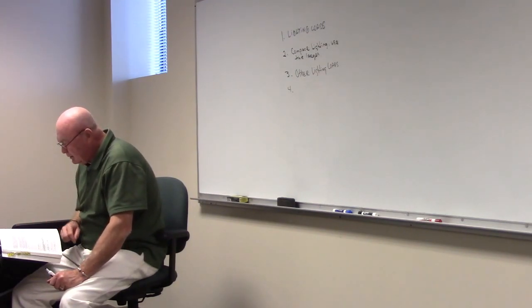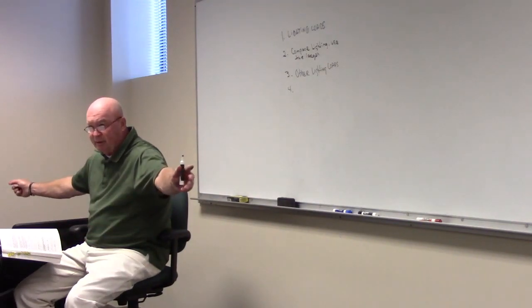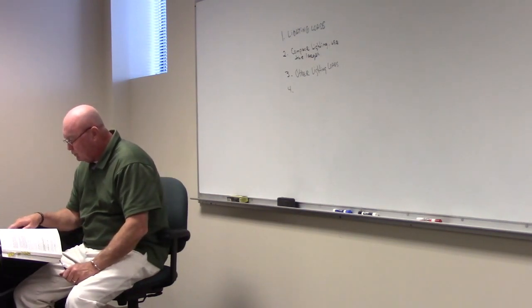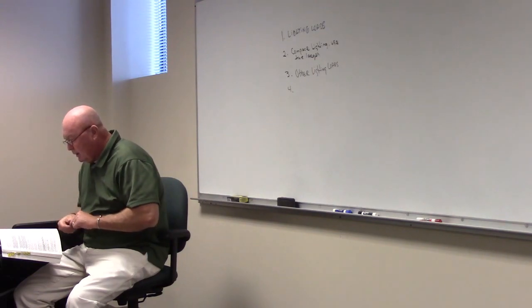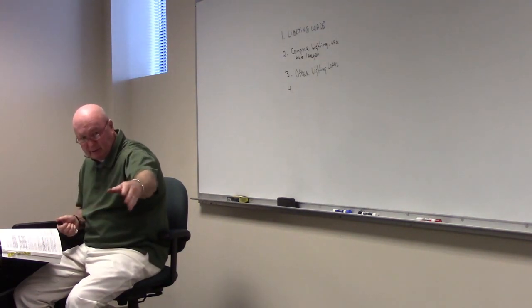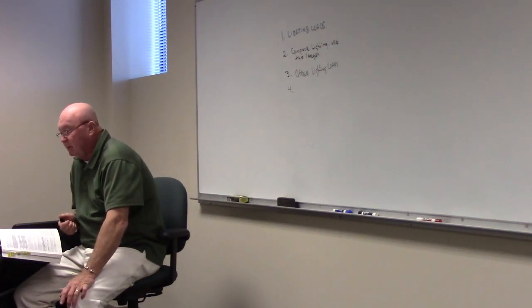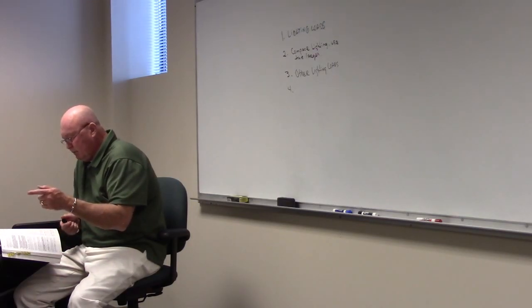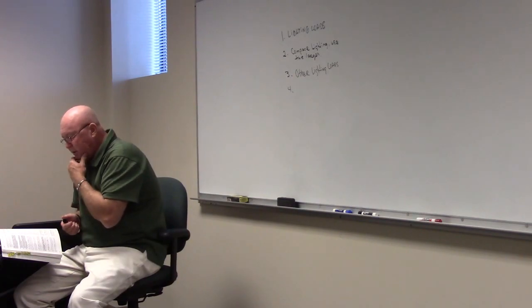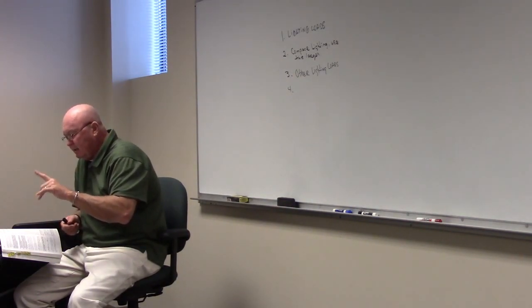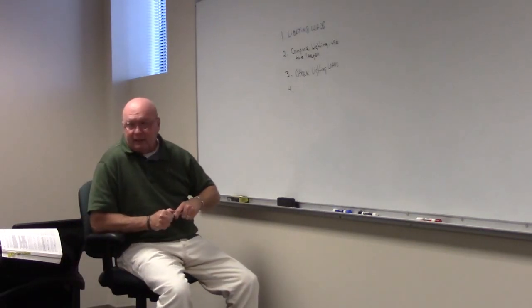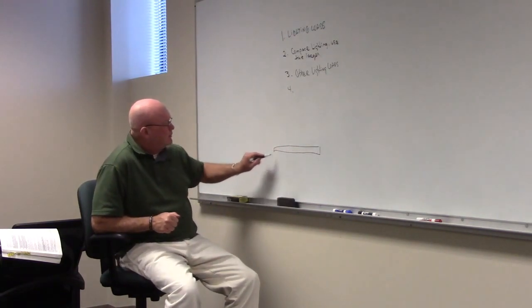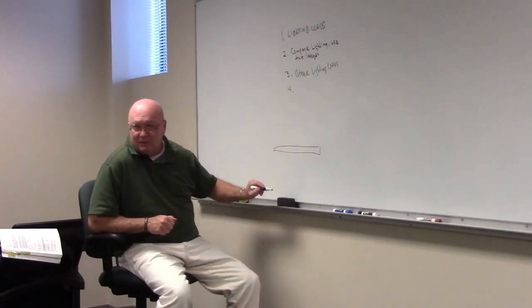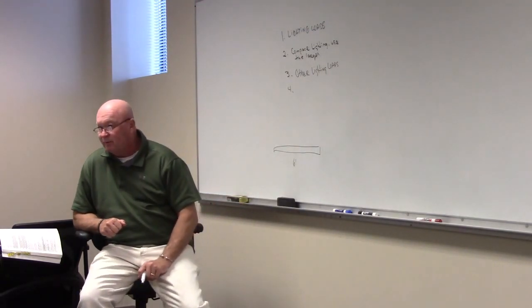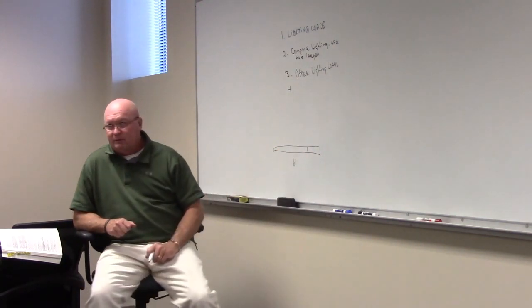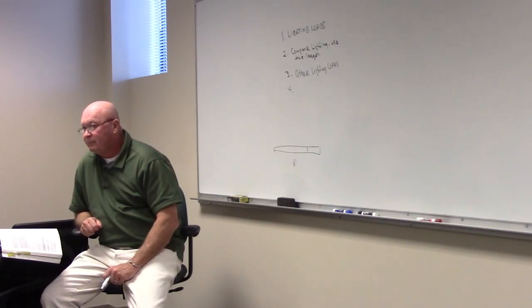If you look at H there, in other words, you have a multi-outlet strip on the wall. If you look at the rule there, it says for every 5 foot, by the way, a general purpose duplex outlet is 180 volt amps, 180. You want to know that. And because of that, if you look at rule number 1 under strips there, for every 5 foot or fraction thereof, you have to count it as 1 outlet. So here's the thing. Multi-outlet strips usually come 6 foot long, typically. Let's just say it is anyway. So it's 6 foot. So how many volt amps is this multi-outlet strip, by reading that rule there?